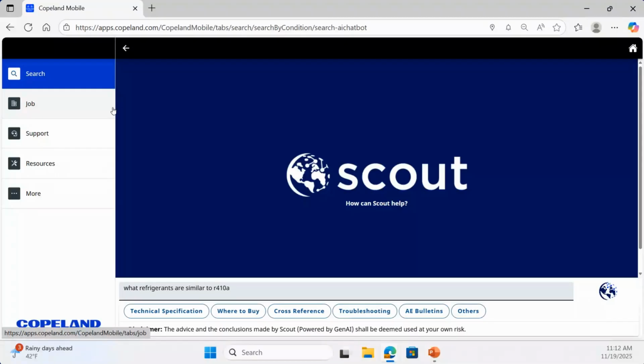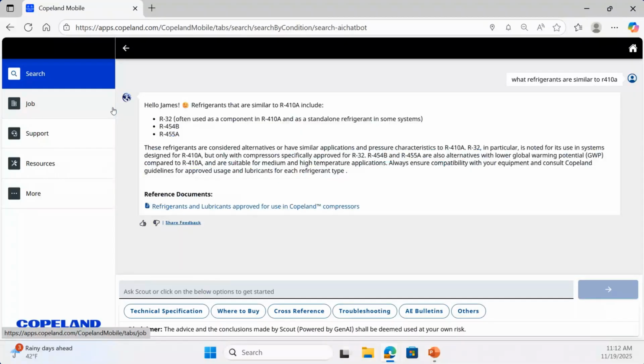I think most folks know by now R410A is a special refrigerant. There's nothing quite like it. It's got a very high pressure range, so there's not really a replacement for it. It is not a retrofit refrigerant in any way, but there are refrigerants used in similar situations. It lists some of that, mostly the A2L versions of the refrigerants here.